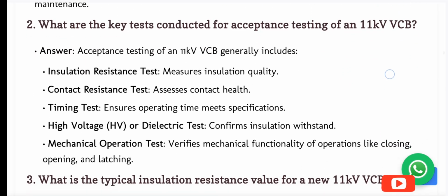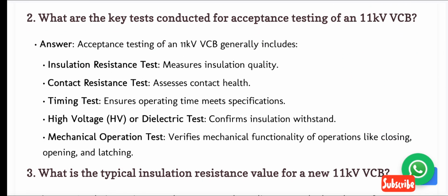2. What are the key tests conducted for acceptance testing of an 11 kV VCB? Answer. Acceptance testing of an 11 kV VCB generally includes: insulation resistance test. Measures insulation quality. Contact resistance test. Assesses contact health. Timing test. Ensures operating time meets specifications. High voltage HV or dielectric test. Confirms insulation withstand. Mechanical operation test. Verifies mechanical functionality of operations like closing, opening, and latching.